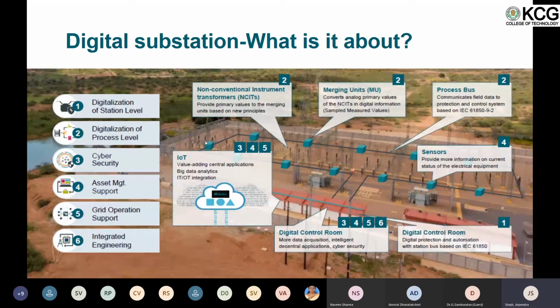There will be separate protection, control and monitoring equipment like fault recorders and different relays, in a centralized relay room or kiosk for control and protection. The field equipment - circuit breakers, CTs, VTs, reactors, transformers - all connect via hard wiring to the kiosk, and from the kiosk, hard wiring goes to the control relays, protection relays, and the control mimic board.